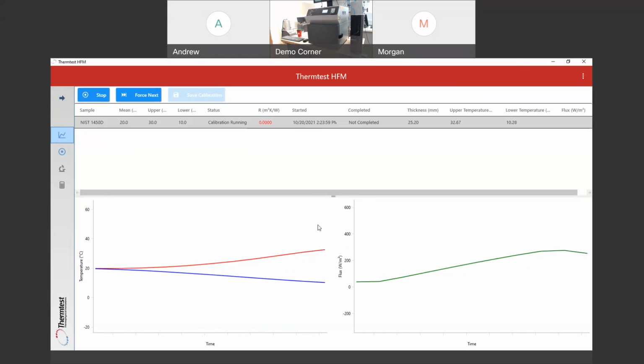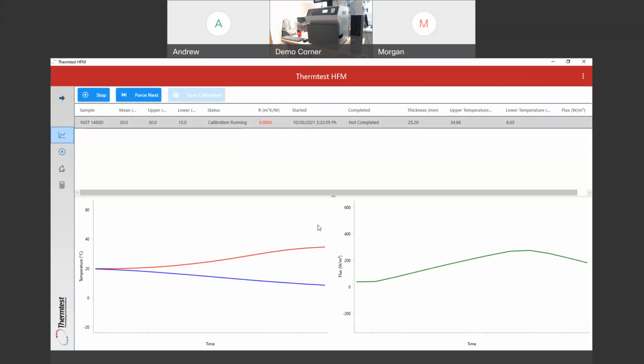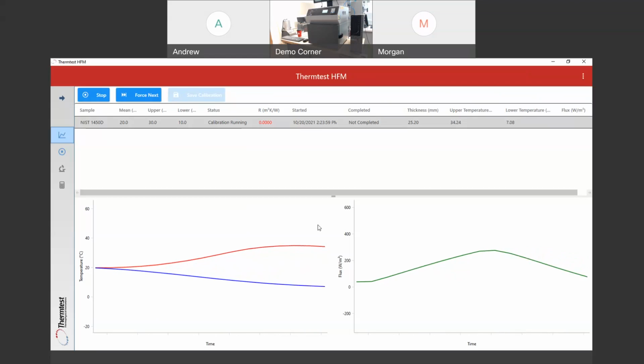There you see the two plates going to their respective temperatures, and on the right side is the composite flux of the flux sensor that's in the plate in the bottom and the flux sensor that's in the plate in the top. And that will look funny until it stabilizes, like it'll just move with the transient temperature that's going on inside, until those plates get to the stable, steady state temperatures, and that flux will start to look pretty stable.